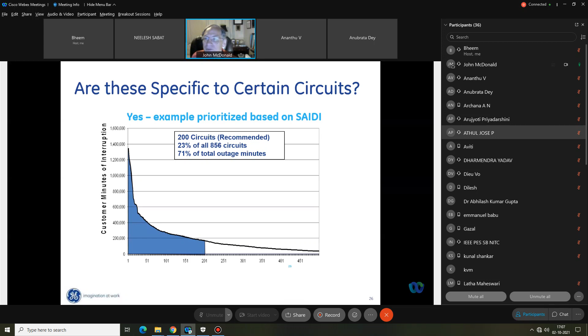Here's a case with a large utility having 856 distribution circuits that wants to improve reliability. The question is, do we need to automate all 856 circuits? That's a tremendous amount of money. When we study it, we find that only 23% of the circuits account for 71% of the outage minutes. So if we automate just 200 circuits, or 23% of them, we're accounting for almost three-quarters of all outage minutes—a much better use of the money.